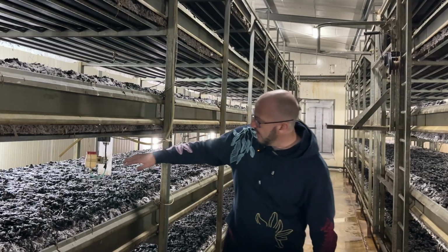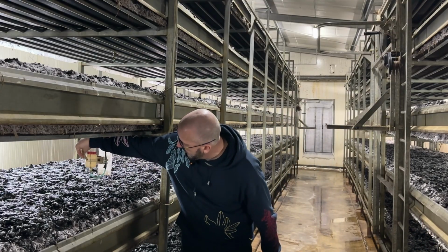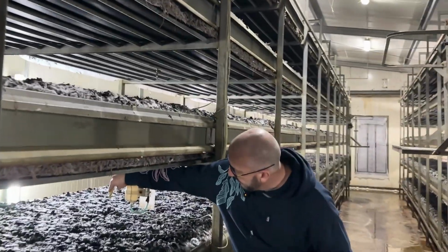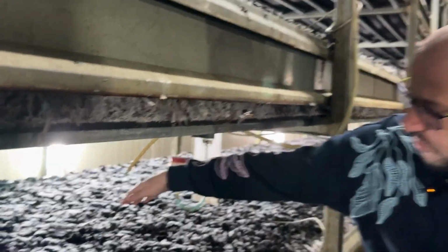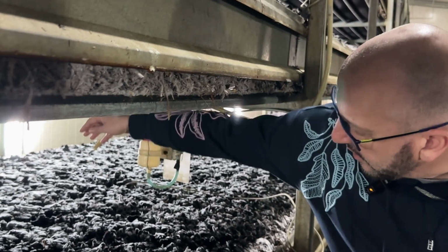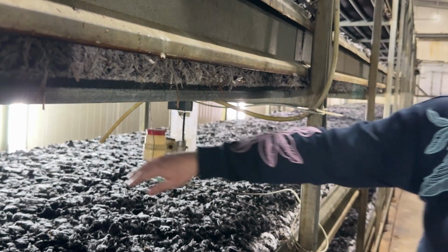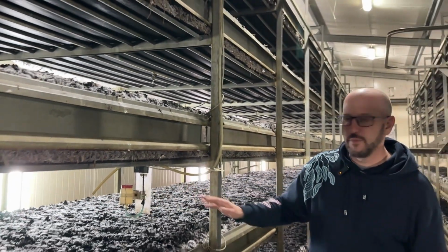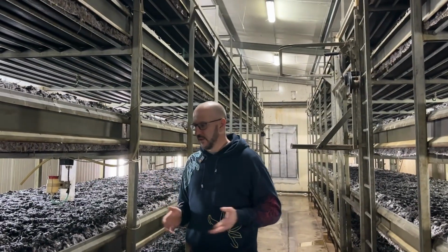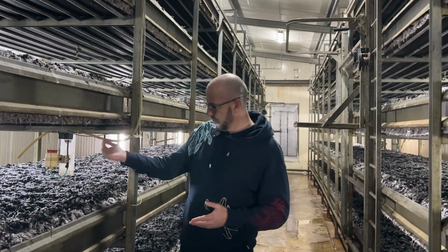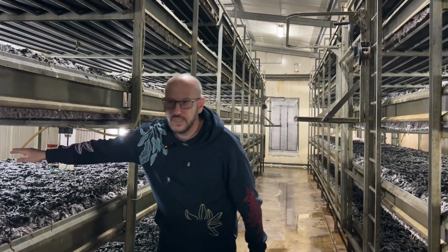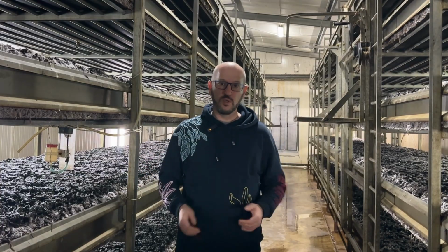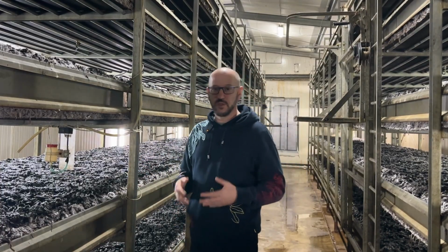Here in this farm you can see a pipe hose situated over the mushroom bed. The closer it is to the bed, the better. Usually you can also see air filters near this pipe, in order to prevent water and particles, dust, casing soil from going into this pipe. And this pipe is connected to a pump, which sucks air from the room and sends it to the measuring device, which measures CO2 levels.